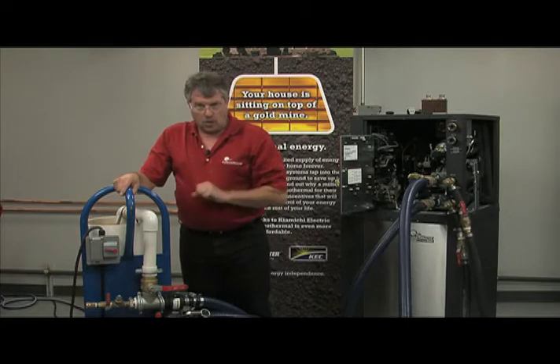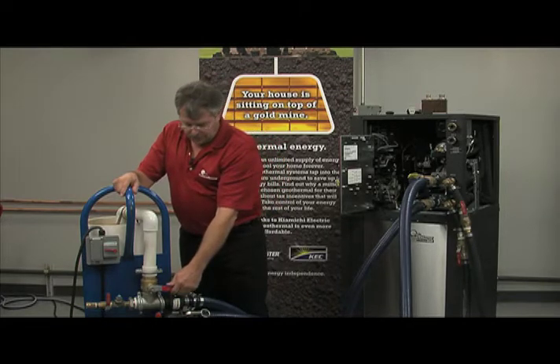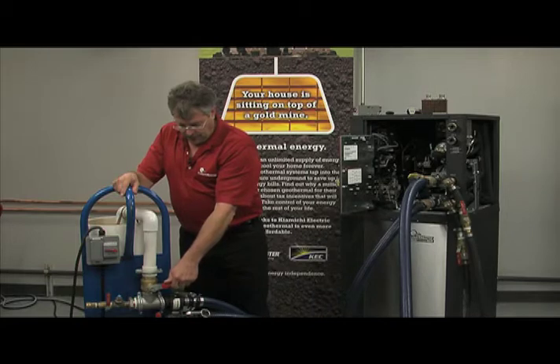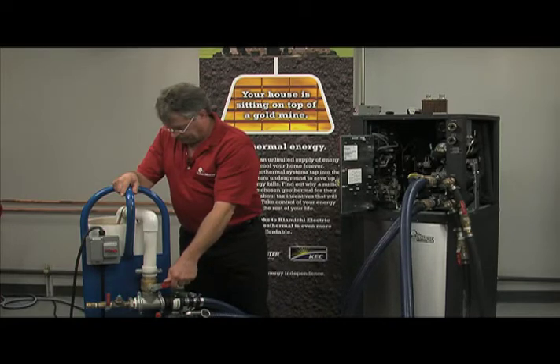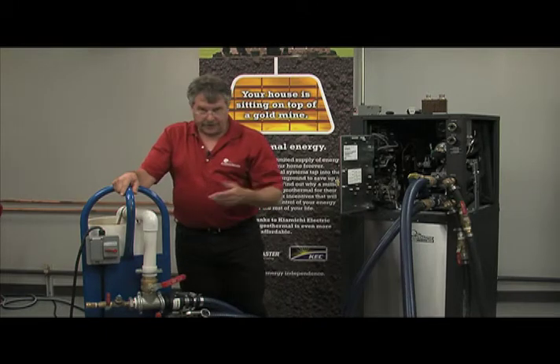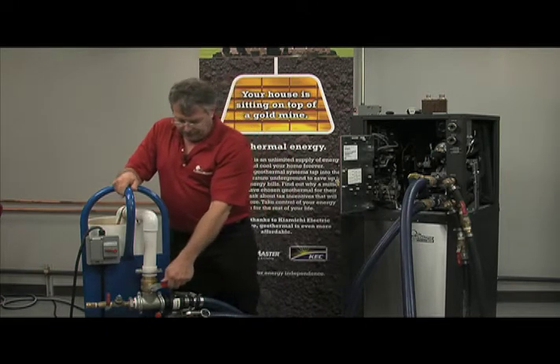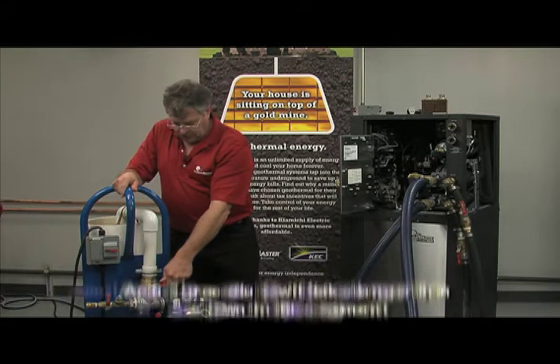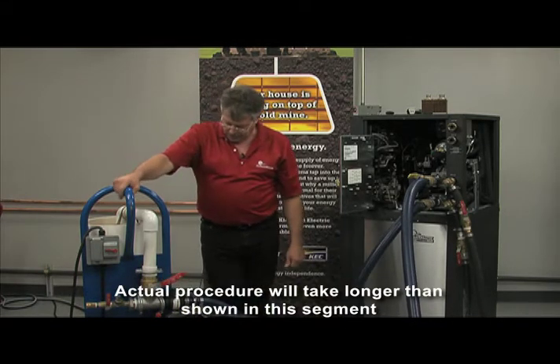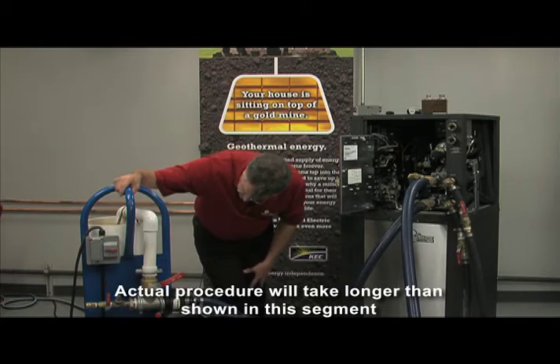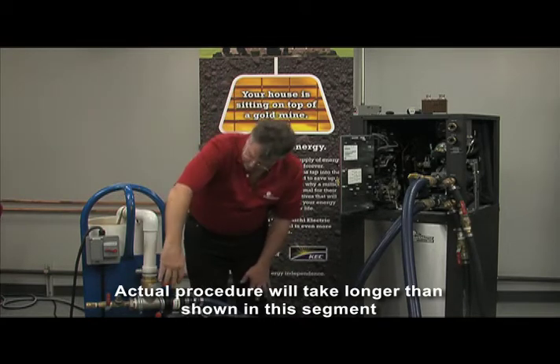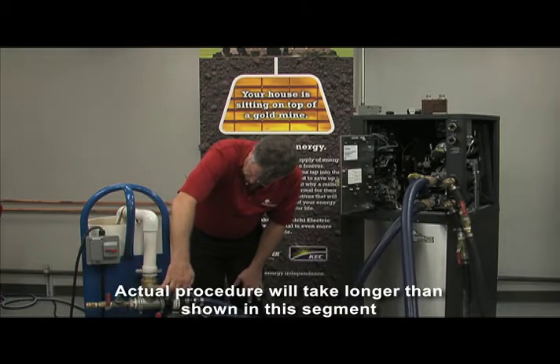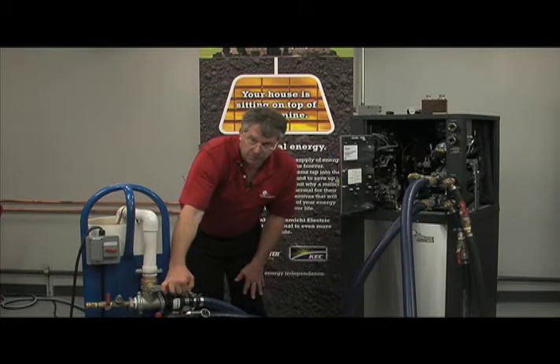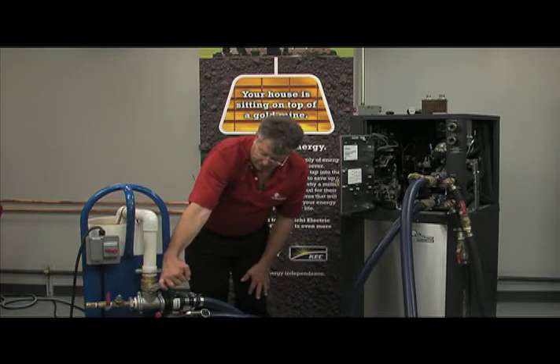I'm getting about maybe 1/4 inch drop on my compression test, which tells me I'm good on the air removal. Since I did apply that deadhead procedure, I'm going to go ahead and let it flow a little bit longer, just to make sure I didn't dislodge any air by doing that compression test. And I've got very, very little movement on my fluid level drop when I do that compression test.